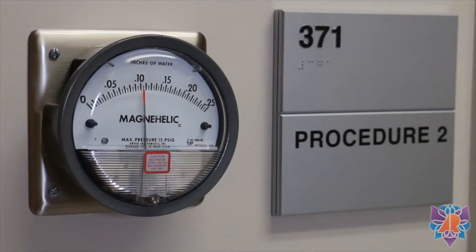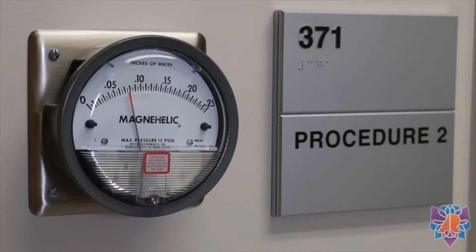Can you give us some examples of other things we do in the lab to protect that space? Well, our patients sometimes notice that we have big barometers outside the doors to our procedure rooms. The reason for that is that we're going to be pushing air always out of the lab, so that when you open that door, you feel the pressure trying to get into that space, because it's trying to blow any less than pure air out of that space.